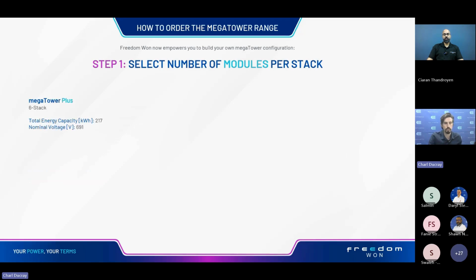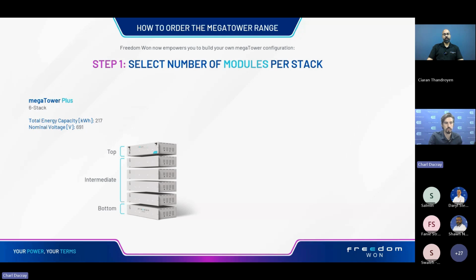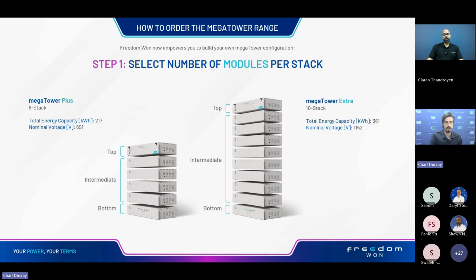So step one in terms of specifying your megaTower is essentially determining the correct battery module stack for your requirements. That will determine your total energy storage capacity per battery module stack, as well as the voltage you're working with. For instance, if you're pairing with commercial inverters, you'll most likely want to stick with the megaTower Plus, whereby your base building block is 217 kilowatt hours and your nominal voltage is 691 volts.